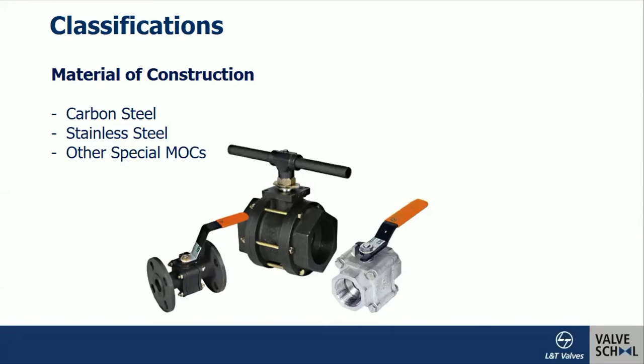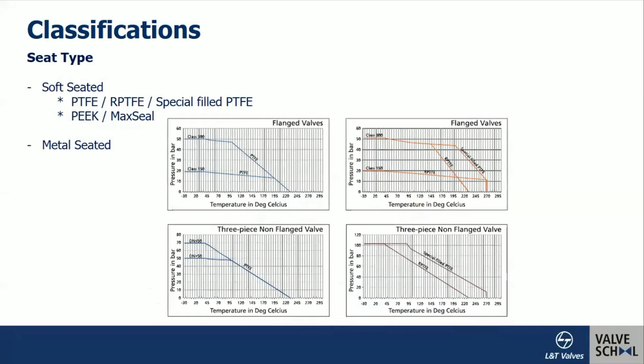Now we look at classification based on seat type. There is a soft-seated valve and a metal-seated valve. Valves like gate, globe, and check are intrinsically metal-seated, while ball, butterfly, and plug valves are available in both soft-seated and metal-seated options. The advantage of soft-seated valves is that they can provide 100% bubble-tight sealing — zero leakage.